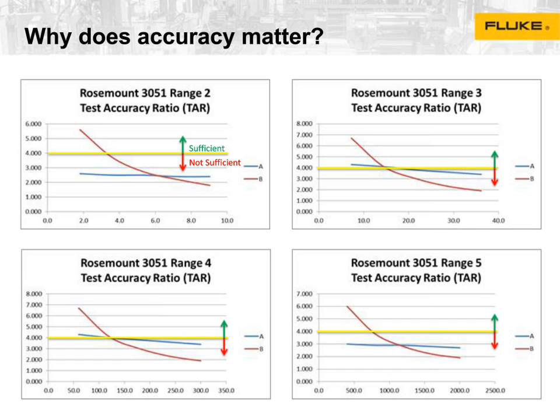And again, they have different methods of specification. Calibrator A is specified as percent of full scale. Calibrator B is specified as percent reading. And what you'll see here is that in the low parts of the range, Calibrator B is very, very good and has sufficient TUR all by itself to maintain a 4-to-1 ratio. But as it gets to the higher end of the range, it gets lower and lower, and in a few particularly bad cases, it gets below 2-to-1. Whereas the one specified as percent of full scale is more consistent.